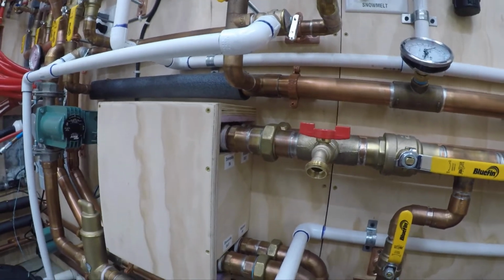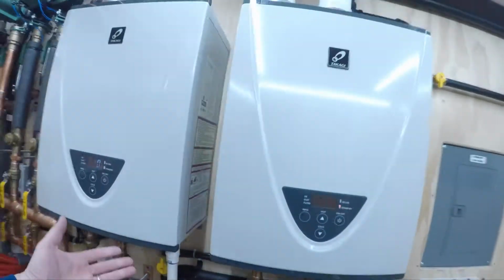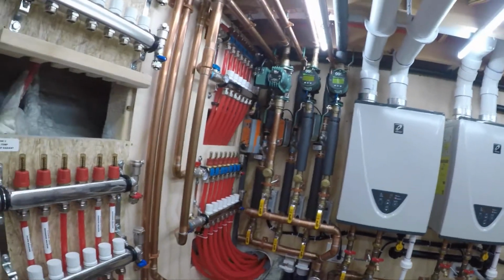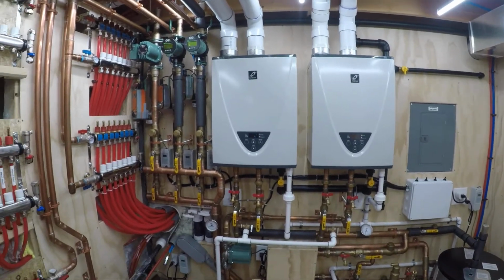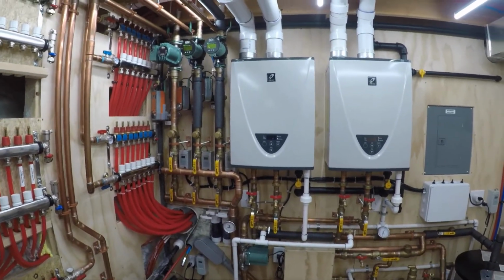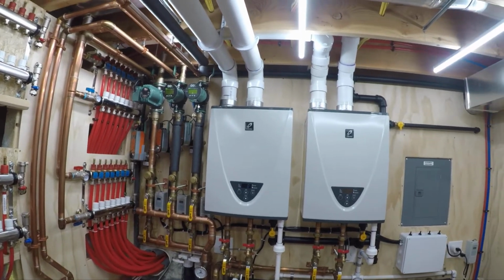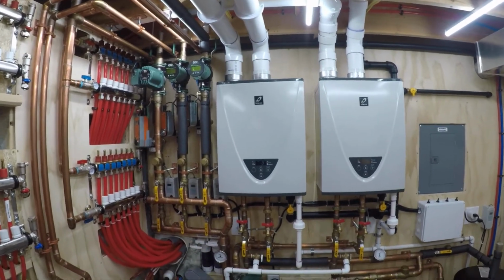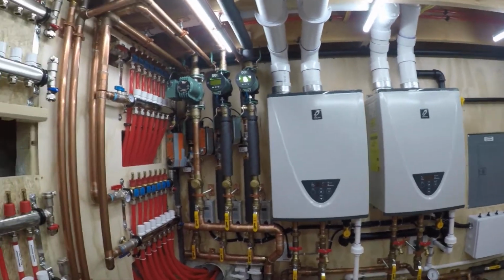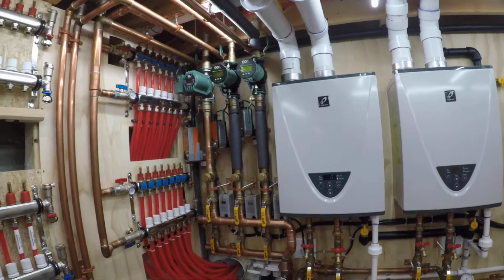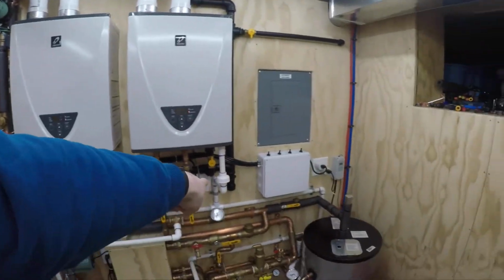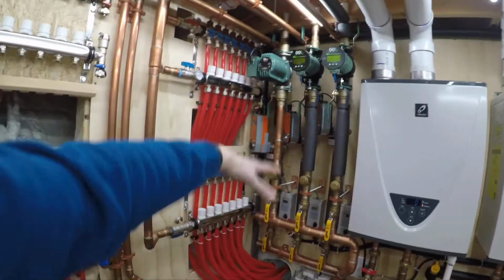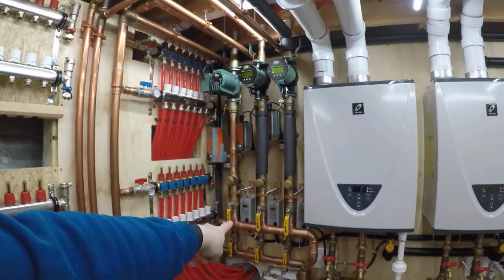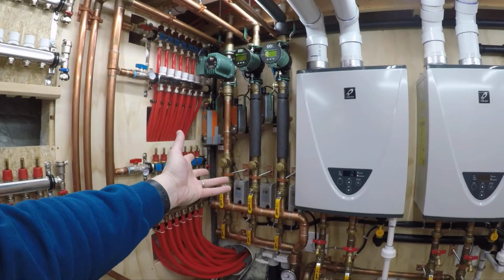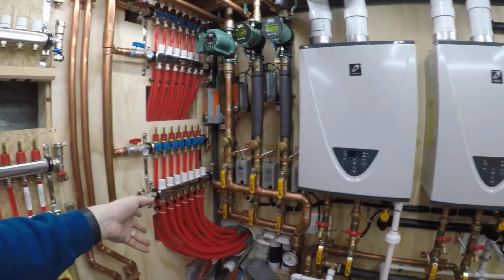Okay, so that's basically how the system works, guys. It looks complicated. It's really not. Once you get it all set up and dialed in, it runs itself. I can be at work, take my phone out, look at the cameras, and say, oh, looks like there's snow getting on the driveway. I go into the Smart Things app, turn on this light switch, that'll energize and turn on everything remotely, the pump comes on, the aquastat comes on. Obviously, if you turned it on right now, it's going to be below 80, so it's going to fire, start circulating the driveway. The heaters will come on.